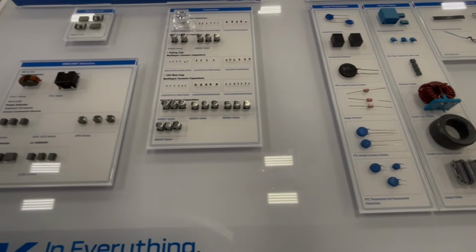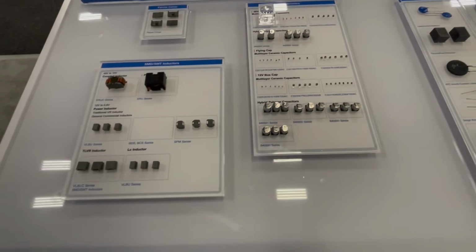Why? Because it's not only a transformer, it's got the power electronics which it utilizes, and that enables a solid state transformer to operate at higher frequencies. Also, because of the power electronics involved, it can transfer medium voltage AC to low voltage DC, medium voltage DC to low voltage AC, and DC to DC. Plus, it also improves the power quality of the system. When I say power quality, it means fluctuations, it means harmonics, and so on. So as you can see, it does a lot more than a standard transformer.